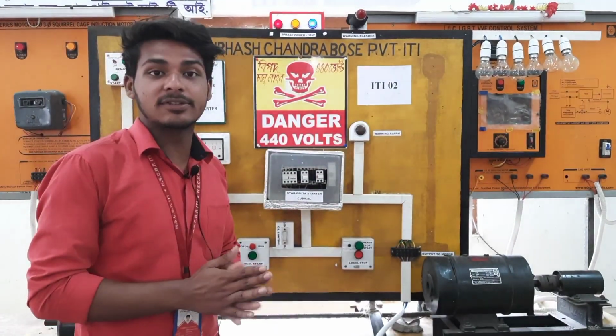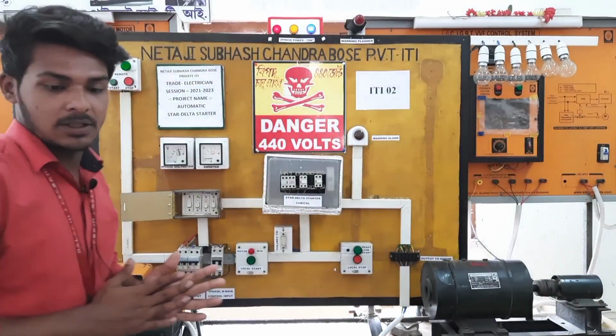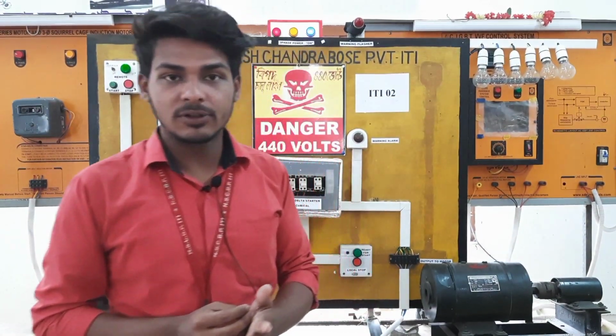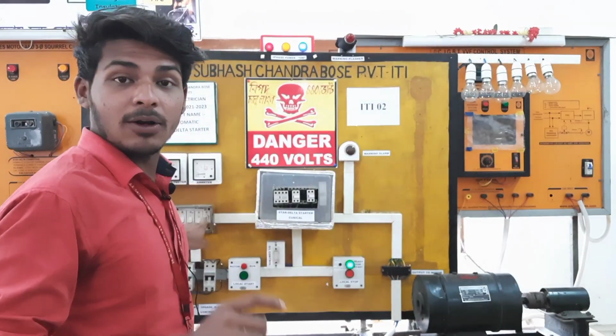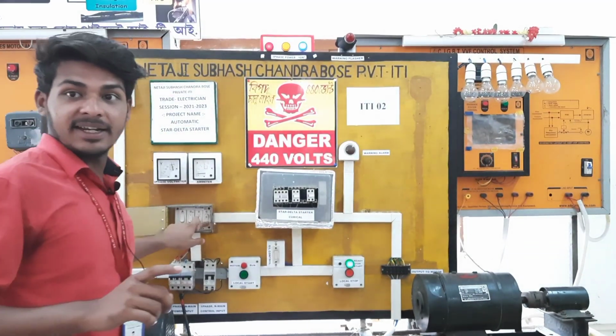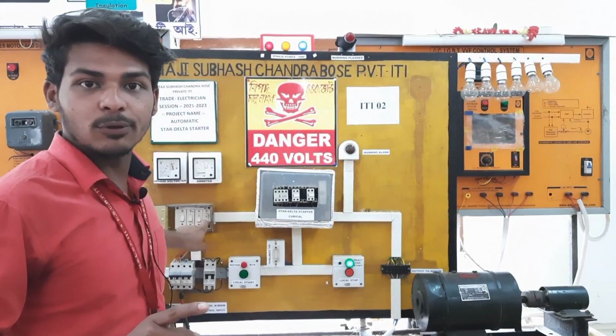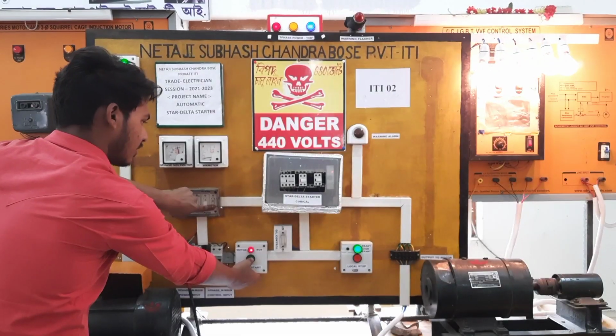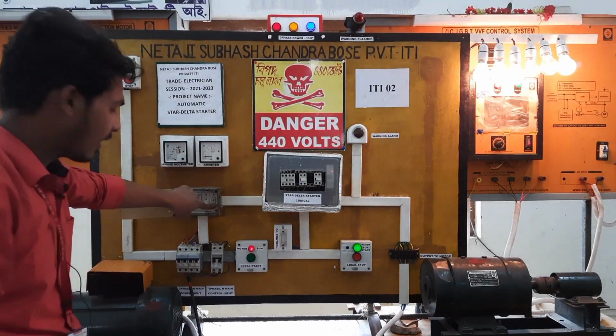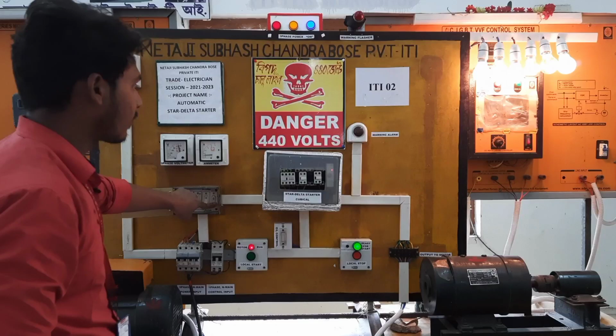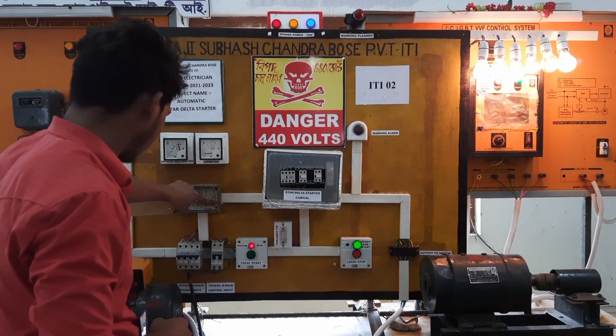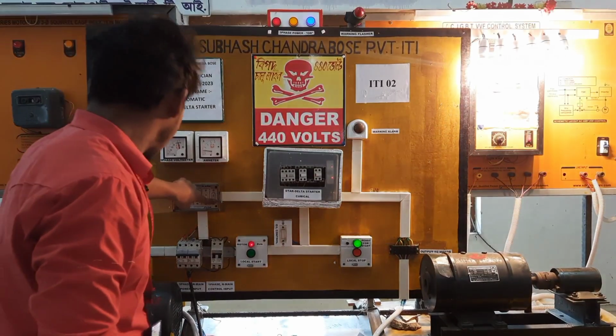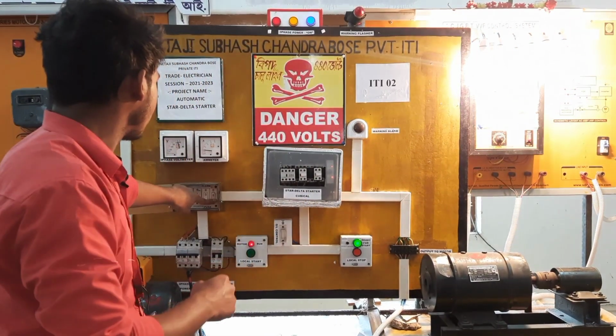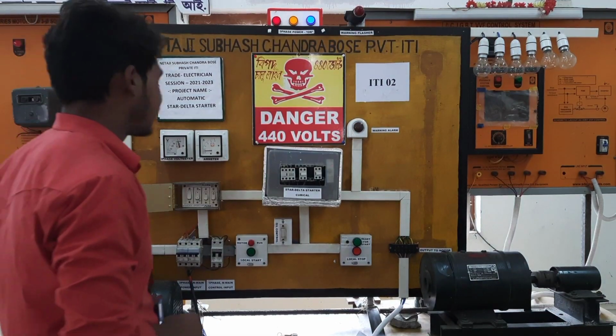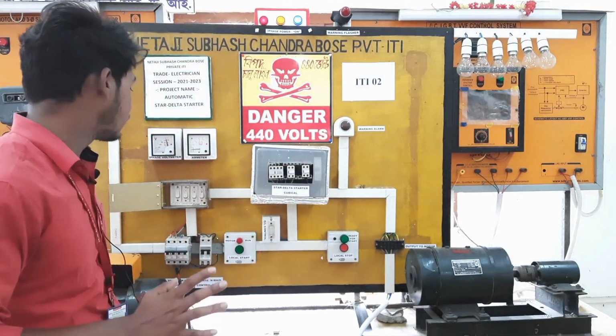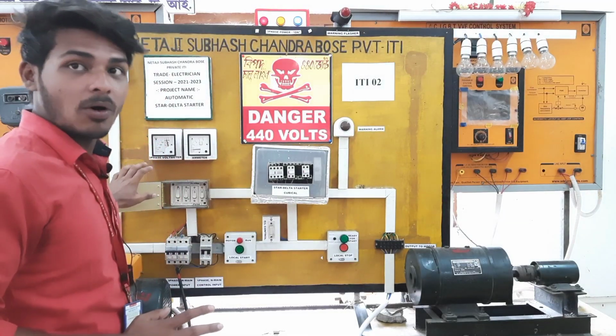Next, specially we have introduced the bypass system to check our control circuit or our operating system. This time control interlock and mode selector should be in maintenance position, overload either off or on position, but our system can be operated. First start, the motor starts and motor running indication is available here. Now in star connection, after a few seconds the motor coil is connected in delta. Our system is okay.